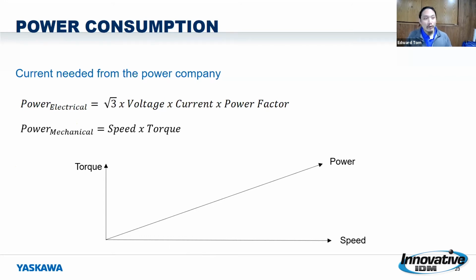Well, how does that equate back to electrical, the VFD portion of it? Well, that is still proportional. So if I've got a motor that's not drawing current, or it's drawing very little current, then I'm going to be pulling very little power. Same with the voltage. Because we're regulating that voltage, if our voltage out to the motor is very low, then that times whatever current is going to result in low power.